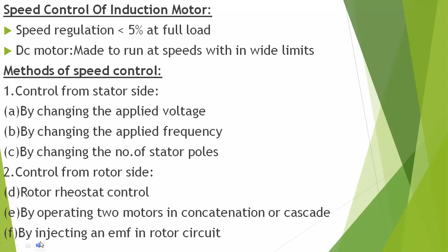First one is by changing the applied voltage in the stator. It seems to be the cheapest and easiest method, but although it is the cheapest and easiest, it is only used rarely because there are some disadvantages. The first disadvantage: if there is a large change in voltage, it gives only a relatively small change in speed. If you change a large amount of voltage, we get only small changes in speed.